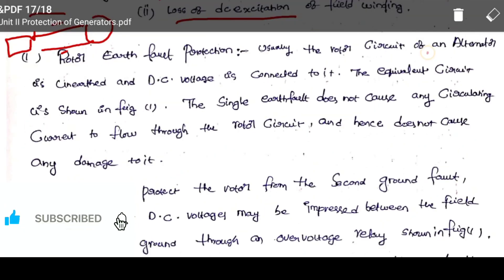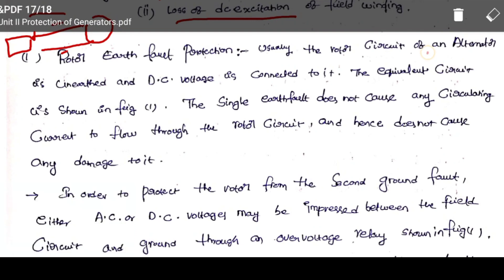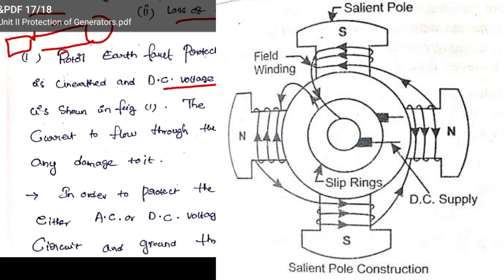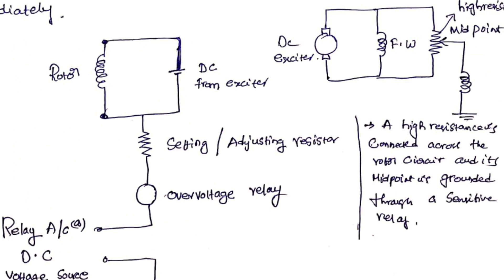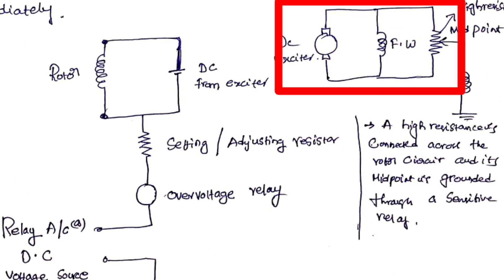Coming to rotor earth fault protection: usually, the rotor circuit of an alternator is not earthed and DC voltage is connected to it — plus and minus are directly given, no earth. The single earth fault does not cause any circulating current to flow through the rotor circuit, and hence does not cause any damage to it.